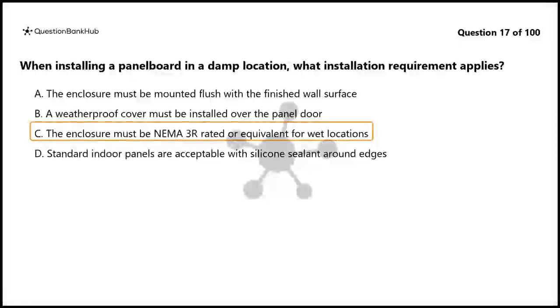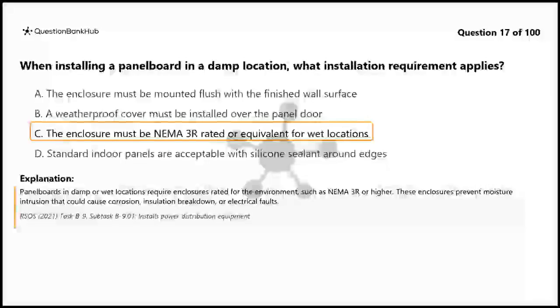The correct answer is C. The enclosure must be NEMA 3R rated or equivalent for wet locations. Panel boards in damp or wet locations require enclosures rated for the environment, such as NEMA 3R or higher. These enclosures prevent moisture intrusion that could cause corrosion, insulation breakdown, or electrical faults.